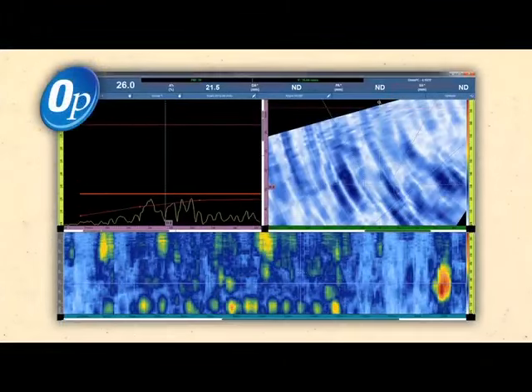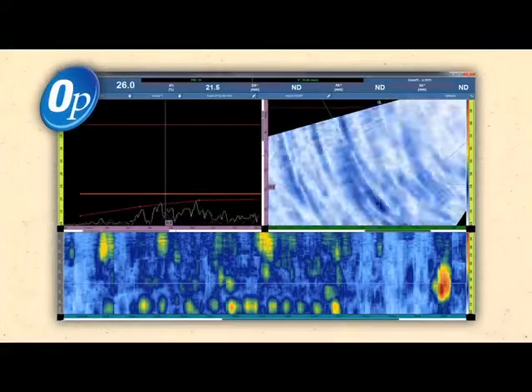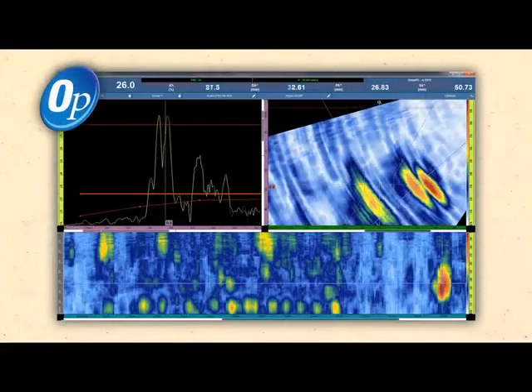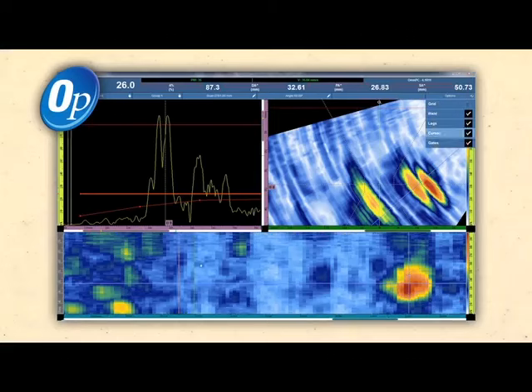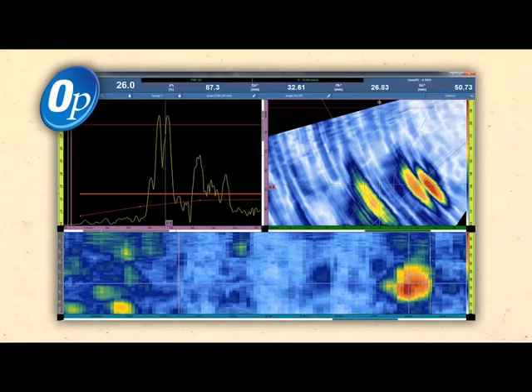OmniPC allows OmniScan data to be analyzed on a computer with the same software interface as the instrument. In this example, a 2 MHz A17 DMA probe detects ID-connected thermal fatigue cracking in the heat-affected zone of an Inconel weld and base material.